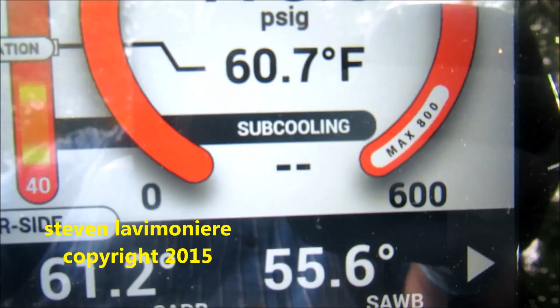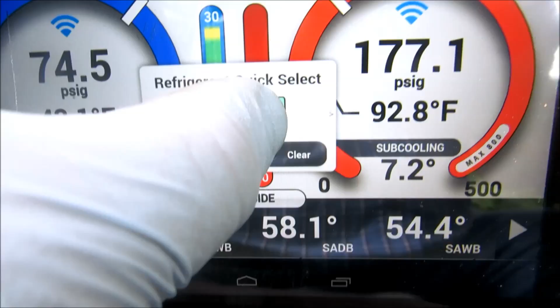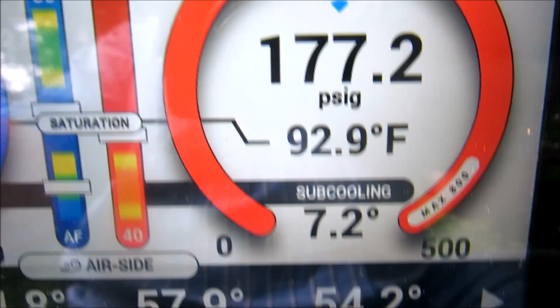Let's give it a little bit and see what happens with our subcool. Alright guys, I had to change it to R22. It's set for 410A or 22, whatever's easier. So it is a 22 system, that's why I had no subcooling before.